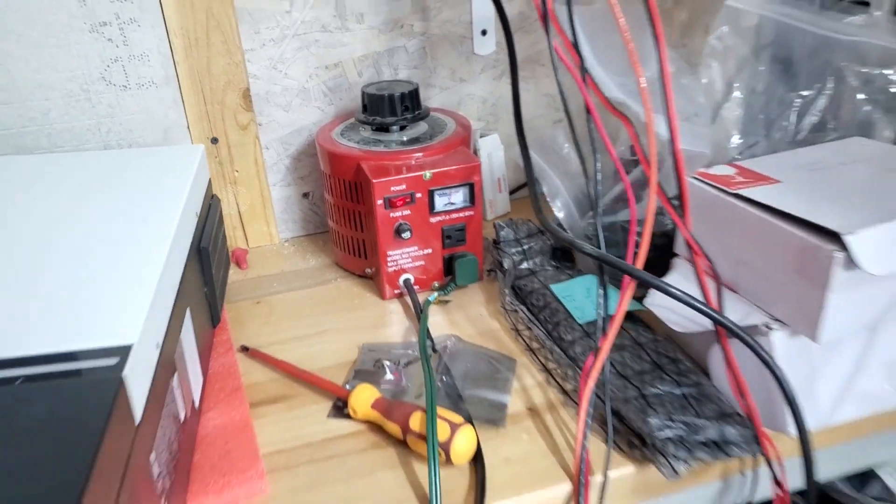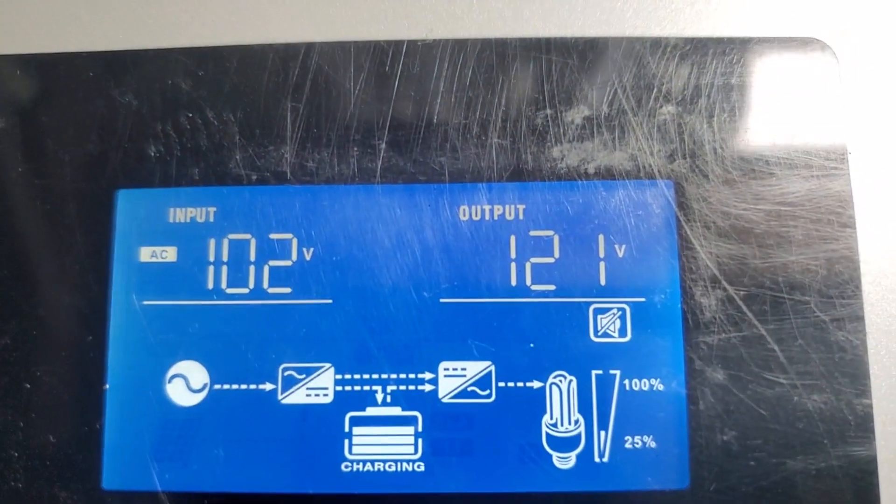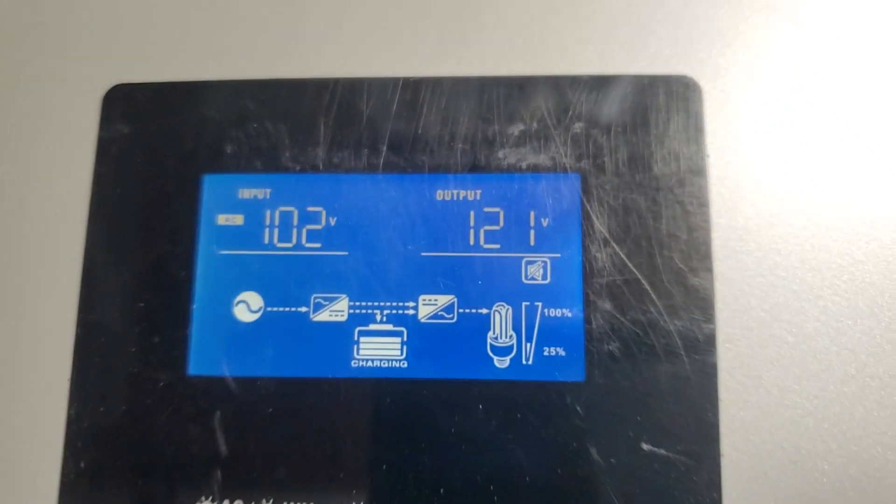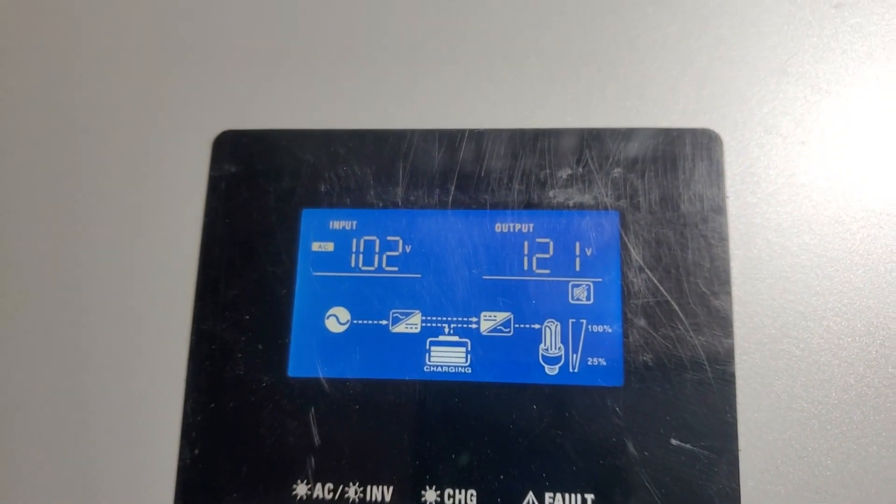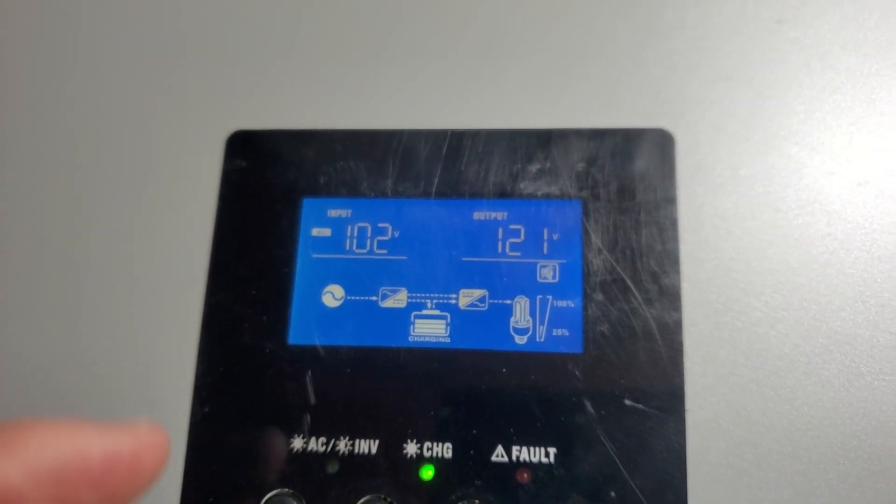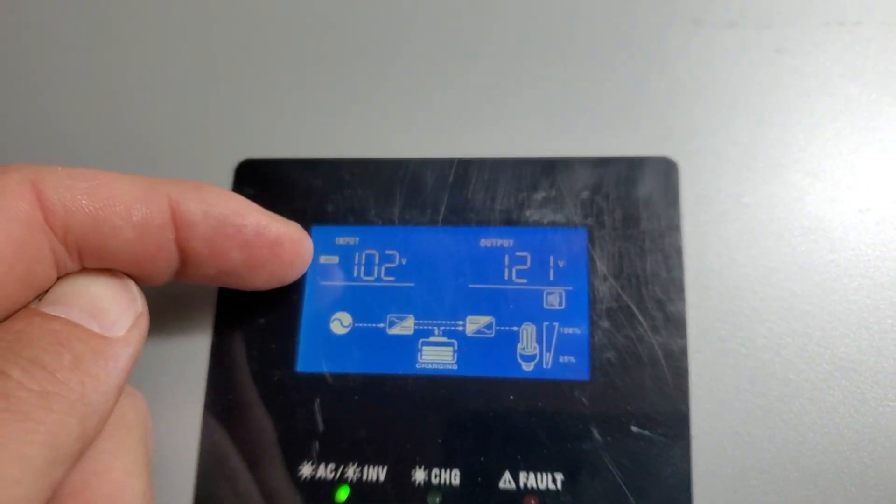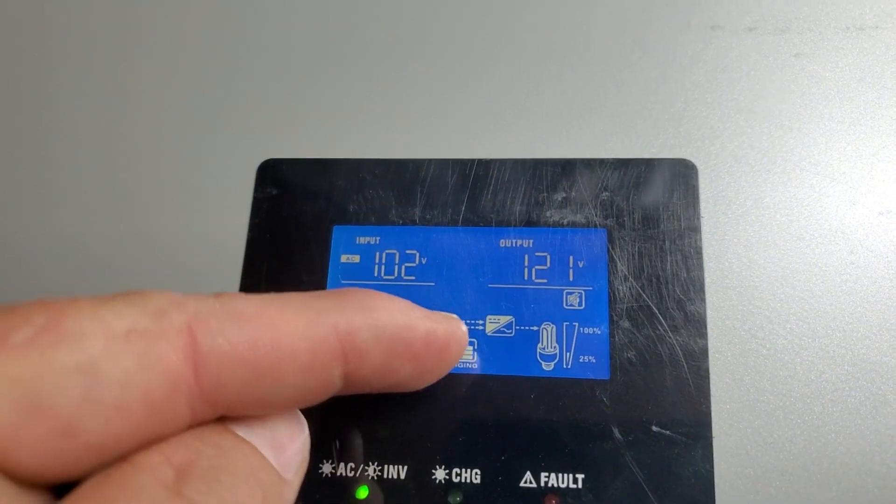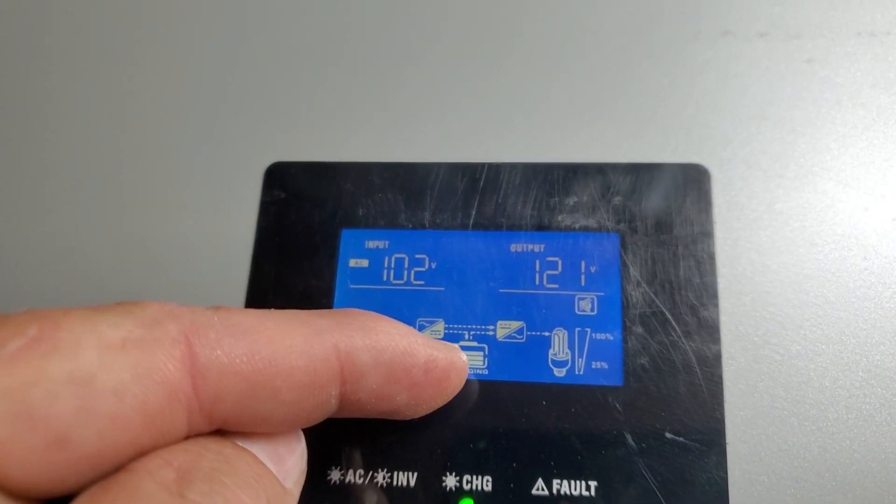Right now I'm showing you we've got 102V input, and this inverter has got double conversion. In other words, it'll take the AC input voltage, it'll convert it to DC, and then the DC will run back through the inverter and give you AC output.